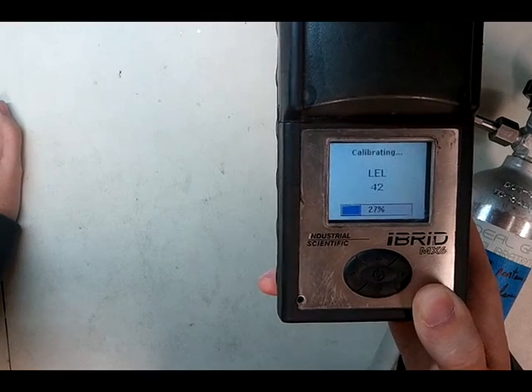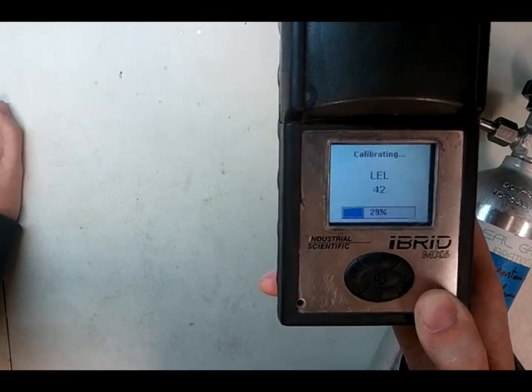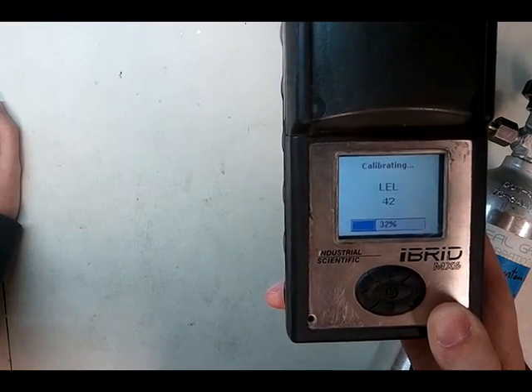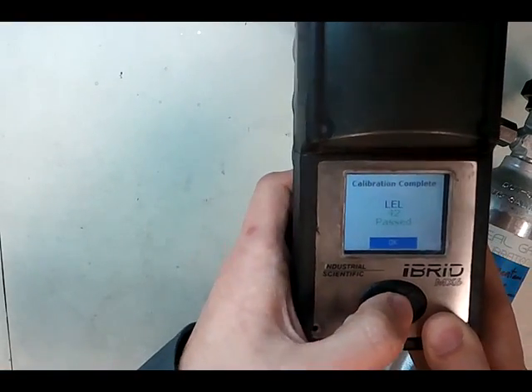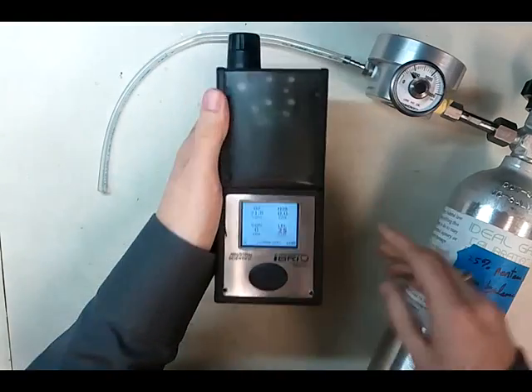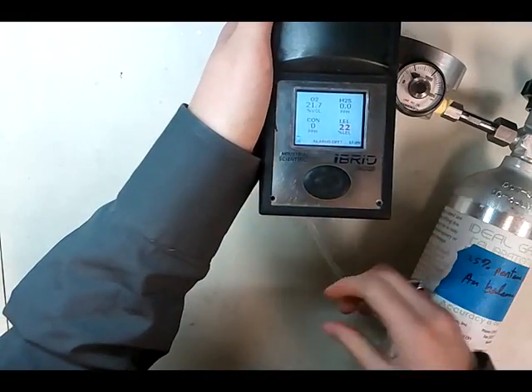Judging by this, the LEL sensor doesn't appear near death at all. It's actually working rather well and has quite a while in life ahead of it. Now it passes with 42. We'll take the gas off and let this air out. You'll notice it shows 25% LEL nicely.